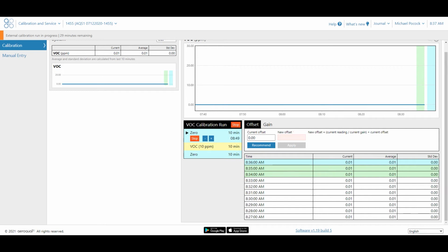The two things that you want to see when you're calibrating is that you get a stable number. So it's around the same number, plus or minus 0.1 ppm when you're working with the VOC H module at 0 here. So we're well within 0.1 ppm. Our standard deviation is actually just saying how different are the last 10 numbers here. So if you're doing a full calibration, you should wait for 10 minutes, and that standard deviation should be very low, so around 0.02 or thereabouts.